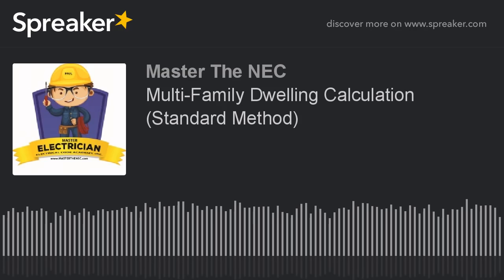Well, in our case, we're going to use 220.61(B)(1). If you look at it, it's talking about electric dryers, where the maximum unbalanced load has been determined in accordance with table 220.55 for ranges or table 220.54 for dryers. So we're able to apply an additional 70%.